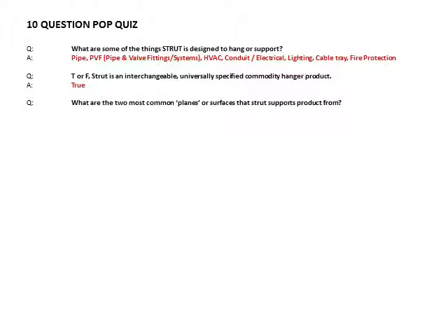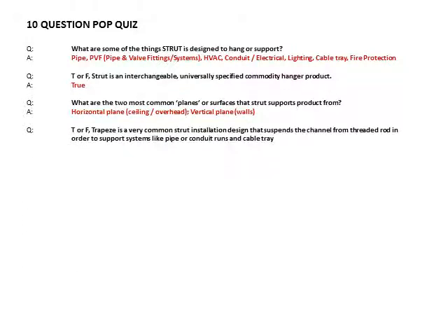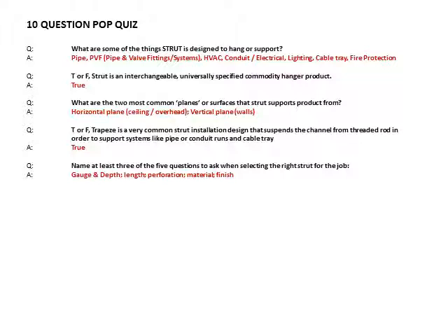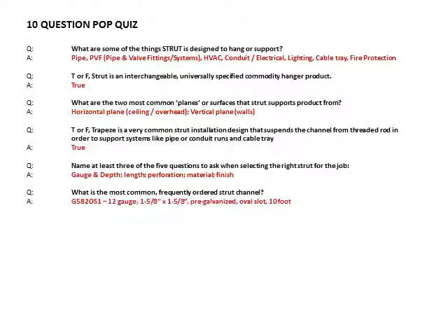What are the two most common planes or surfaces that strut supports product from? Horizontal plane and vertical plane. True or false: trapeze is a very common strut installation design that suspends the channel from threaded rod in order to support systems like pipe or conduit runs and cable tray. True. Name at least three of the five questions to ask when selecting the right strut for the job: gauge and depth, length, perforation, material, finish. What is the most common, frequently ordered strut channel? G582-OS1: 12-gauge, 1-and-5/8-inch by 1-and-5/8-inch, pre-galvanized, oval slot, 10-foot.